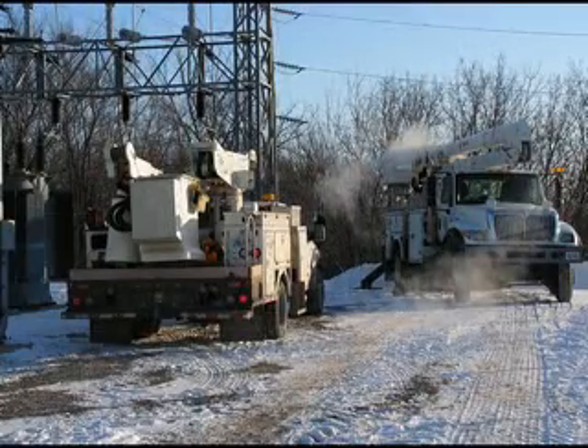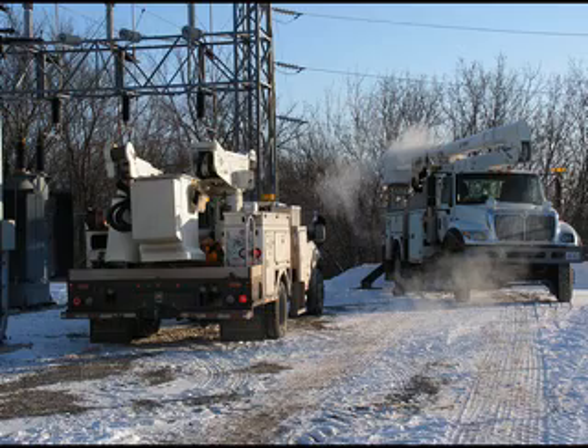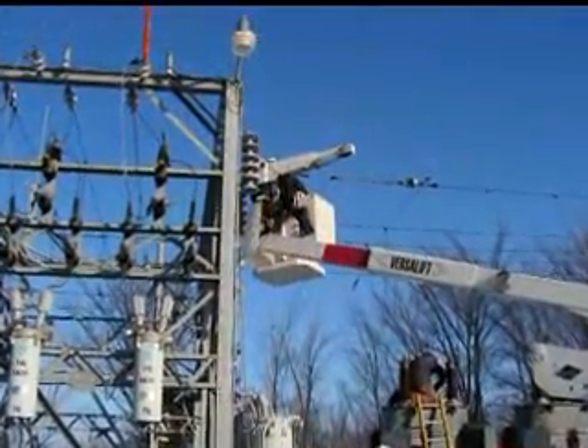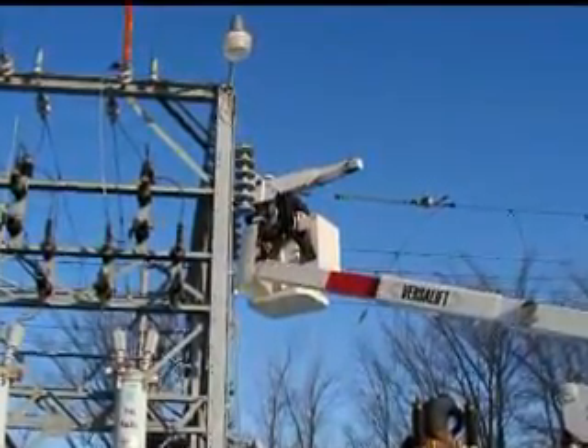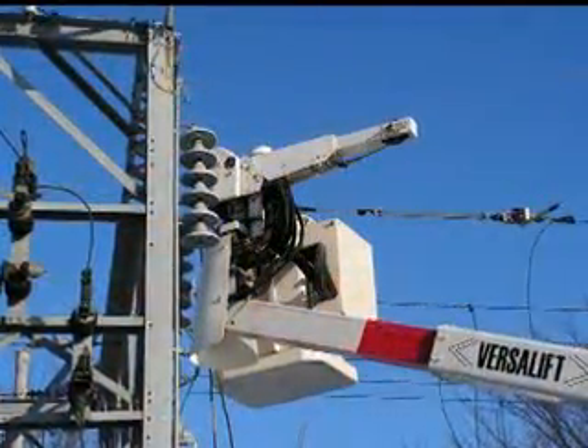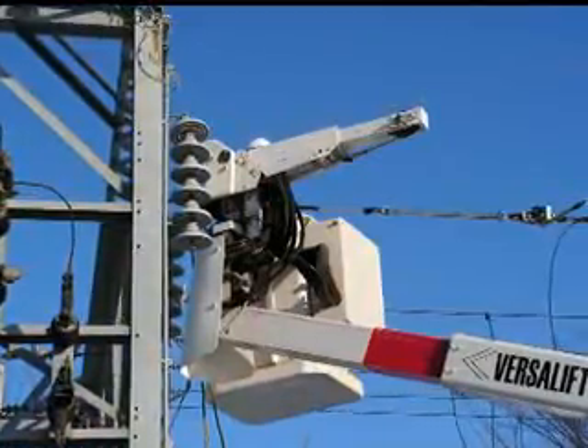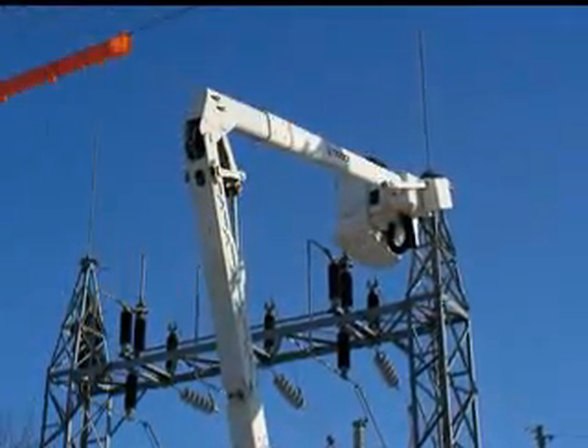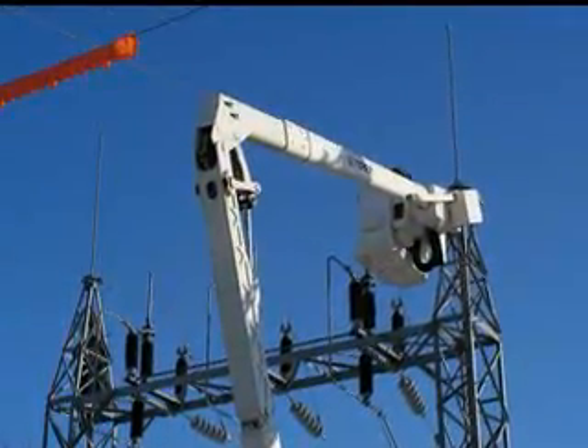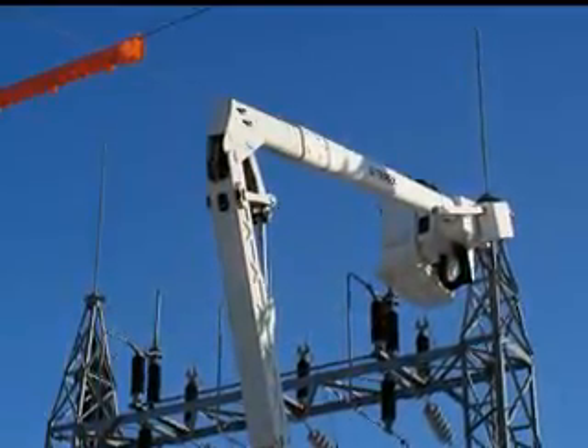Safety of the work crews is the top priority at any Steele Waseca work site. Once the power was switched and the substation shut down, the next step was to shut off the transmission line that brings power into the substation, followed by installing the necessary grounds to assure everyone's protection.